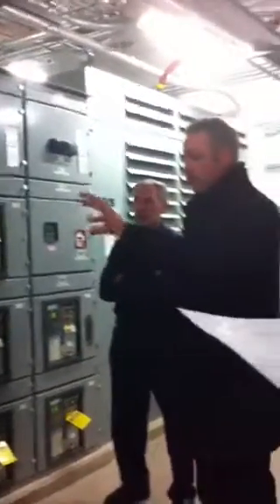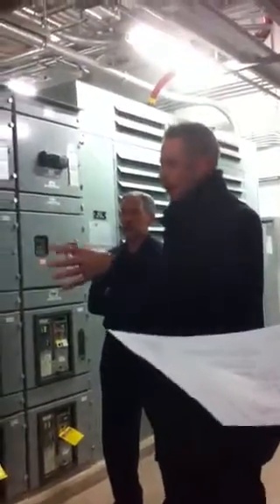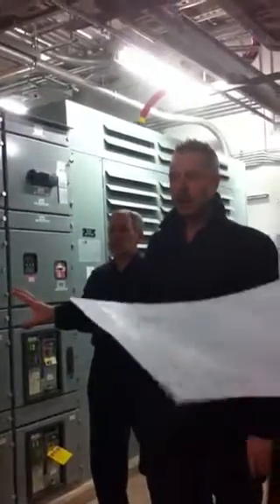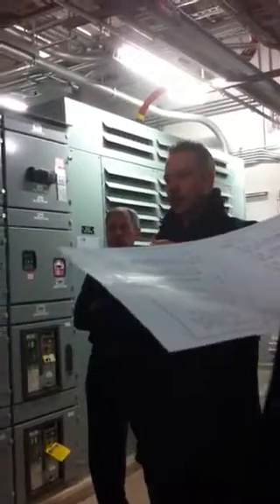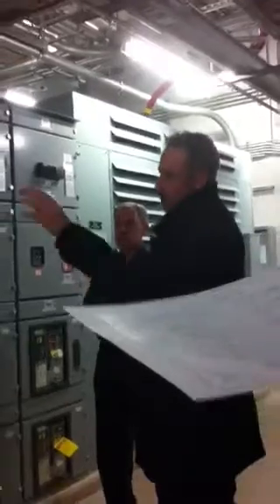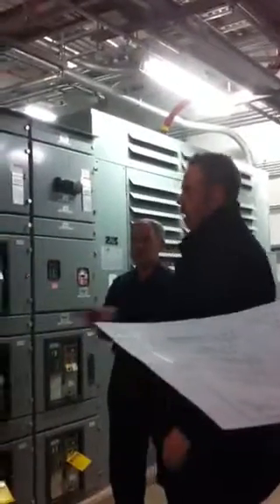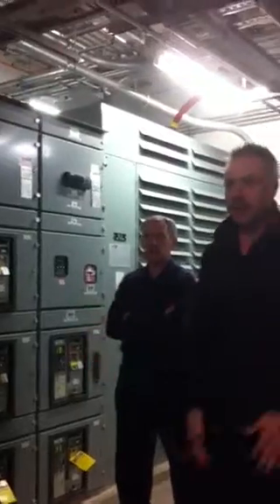In the event that you remove, or lose the transformer, you can close the tie breaker, which physically ties the two boards together, and the loads that were fed from the transformer that was down are now sub-fed from the two boards connected to the remaining transformer. If you lose both transformers, I mean, that's a catastrophic failure. You have bigger issues than worrying about feeding loads in the building.